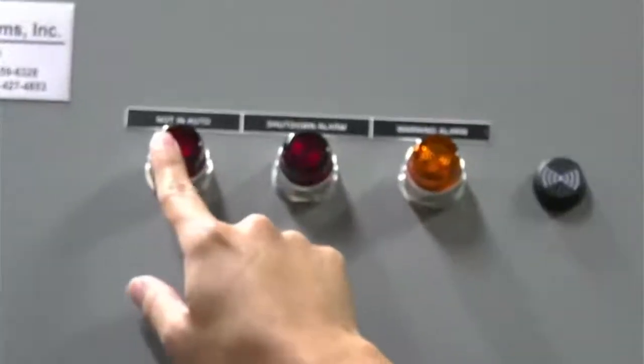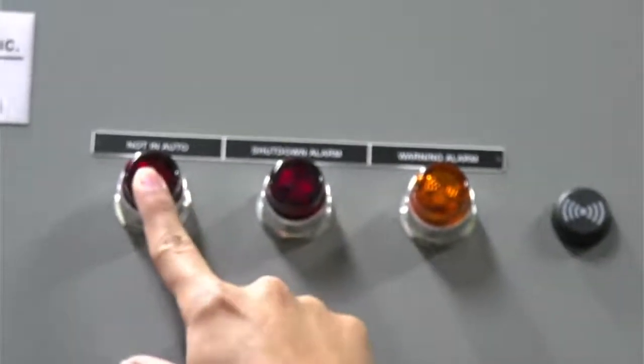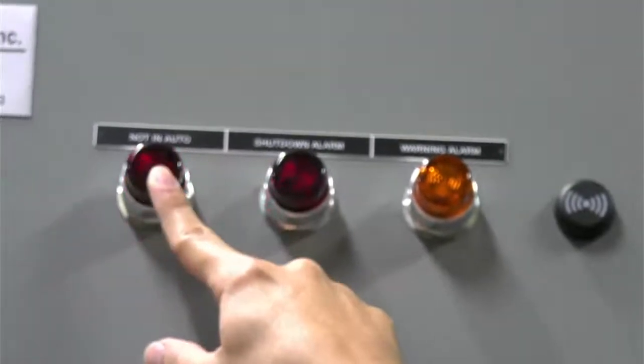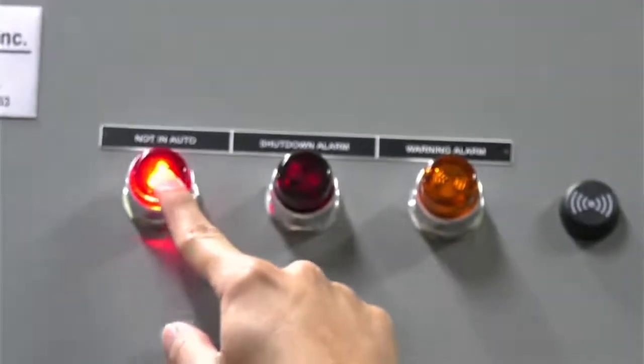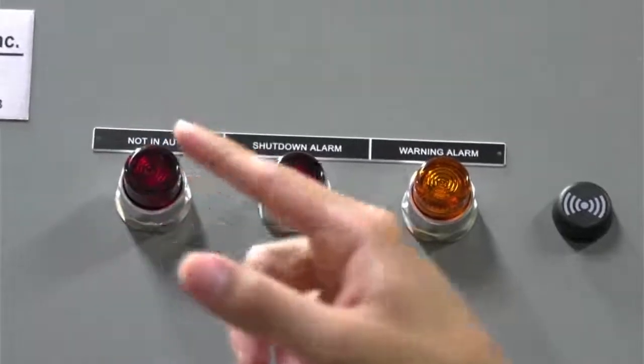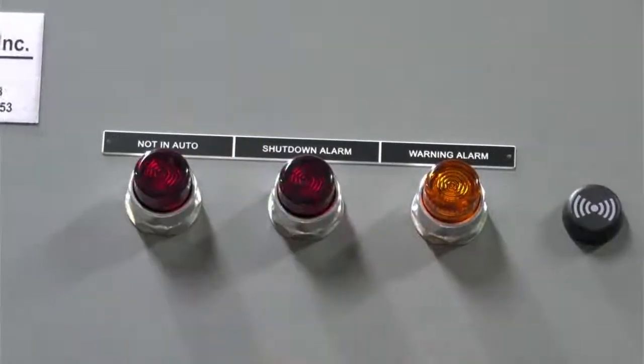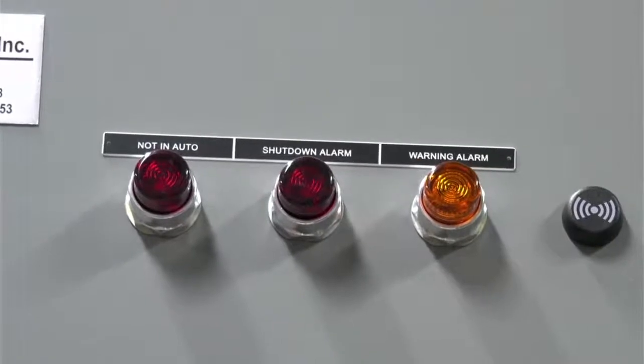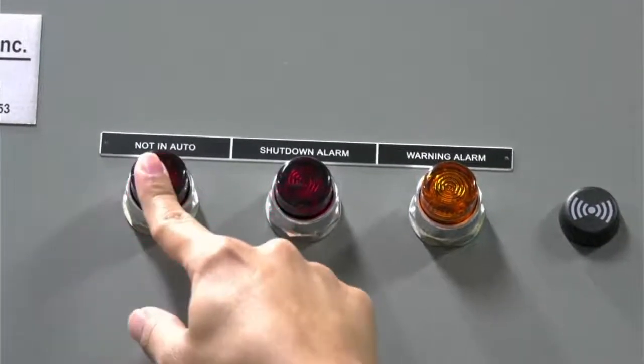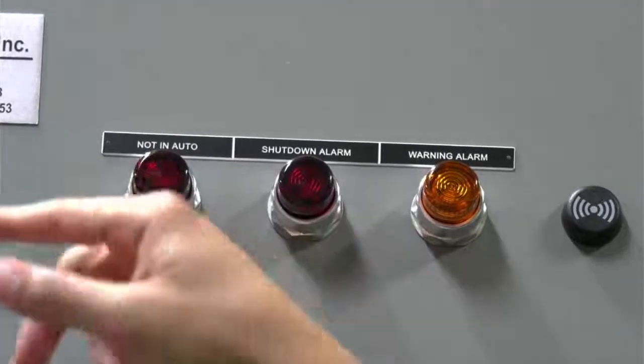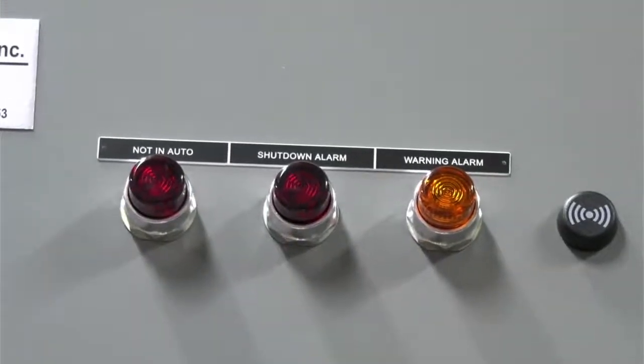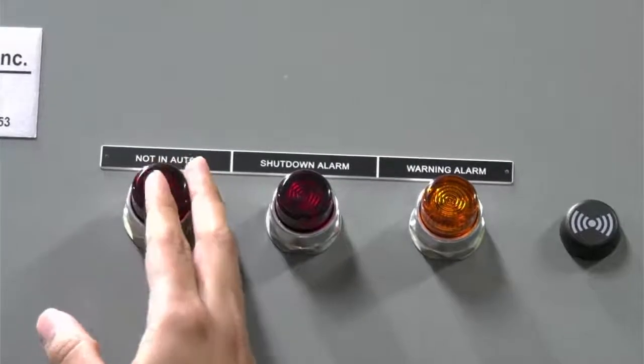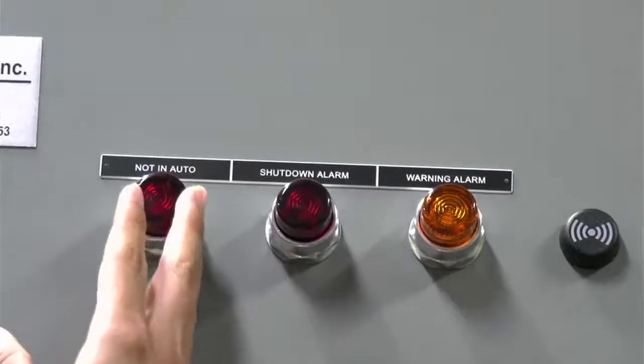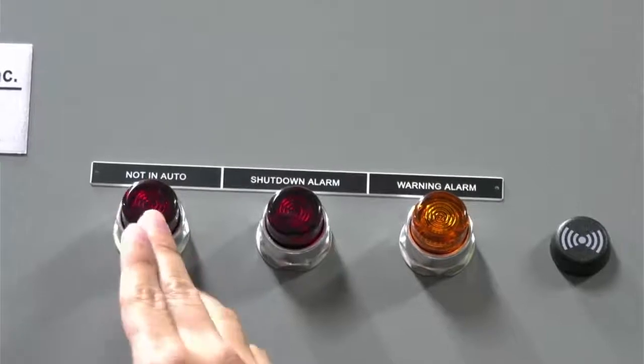Right, this is group number 1. We have 3 pilot lights and 1 buzzer. And basically the first one is to indicate the system is not in auto. You can press the LED, the pilot light, to test if the bulb is working good. It doesn't mean that it's gonna do any action. It's just to prove that the light is working. So system not in auto. When the system is in manual, you're gonna see this pilot light like this.